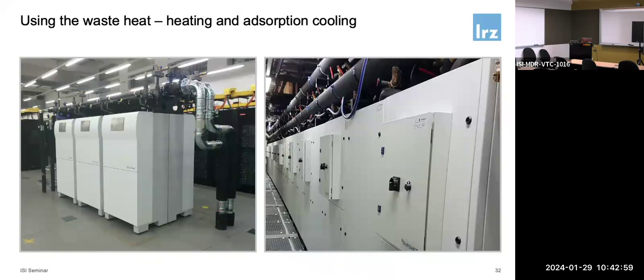So what we do is use the heat from SuperMUC-NG, put it into the system, and generate cold water on the other side. We're actually cooling the cold water system with the waste heat from SuperMUC-NG, which is an interesting effect. There are some efficiency issues here, but it's a research project, that's why we wanted to do it. This is almost the entire length of the building, about 72 meters of infrastructure, and we need about one third of it to feed the waste heat, so there's two thirds left that you could do other things with.